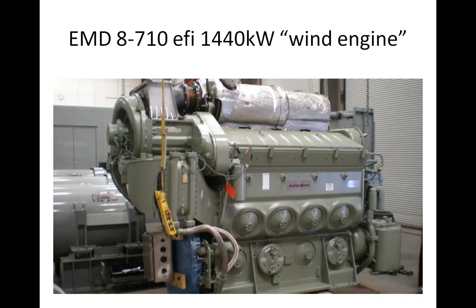It does put some load on the engine and the battery, but we don't shut anybody off. Prior to having this engine and the battery, we'd essentially run a negative reserve on some of our older engines, and if we had a problem, we'd go into a load shed mode because the engine couldn't maintain frequency or voltage, so we'd have to shed a feeder, which wasn't very popular with the community. We were having several partial power outages per year due to wind power. This has really done well for us in terms of fuel efficiency, but also keeping the lights on, which is what everybody wants.